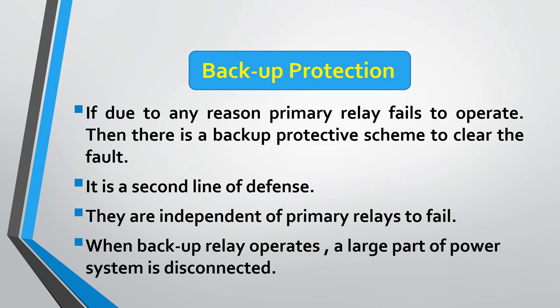Just as in daily life we have a primary plan and a backup plan, in a power system we also have a second line of defense. If the primary relay fails to operate, the backup protective scheme clears the fault. Backup protection is independent of the primary relay and uses different sensing elements. When the backup relay operates, a larger part of the power system is disconnected compared to primary protection.